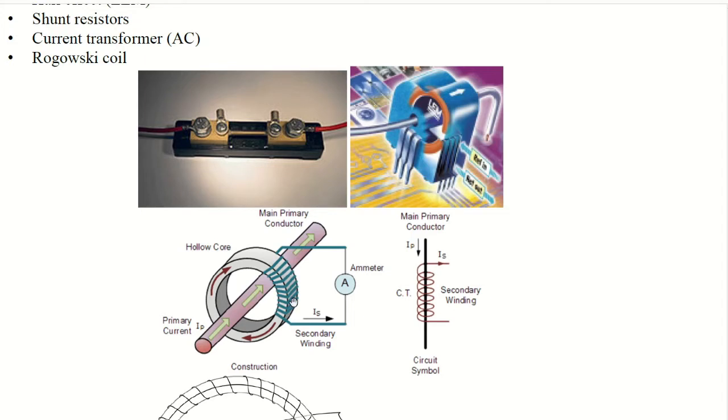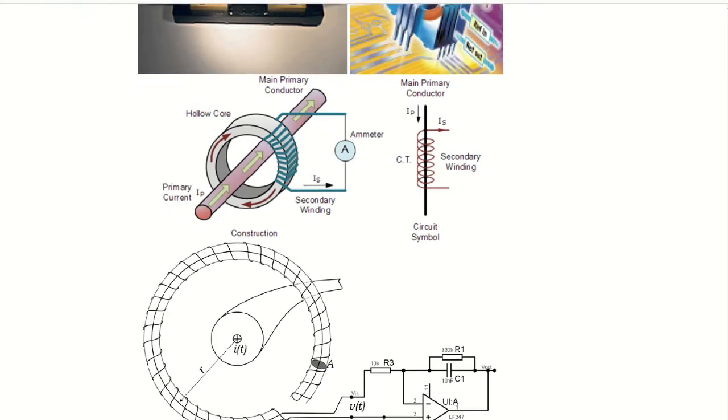So they work between 40 and 65 Hertz. So they cannot measure the DC current, for example. And you have Rogowski coils like this one, used for very huge current.